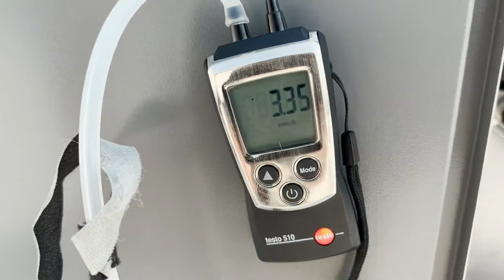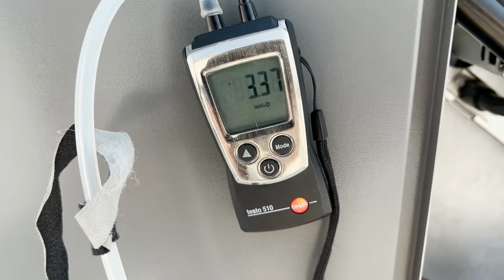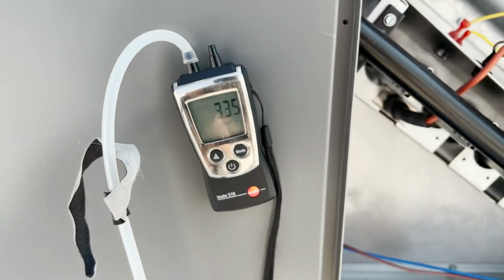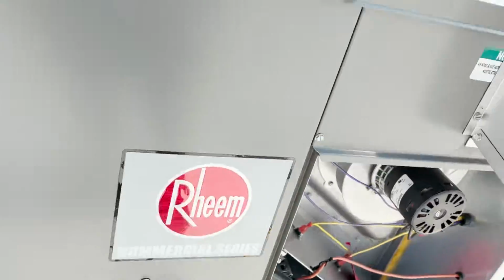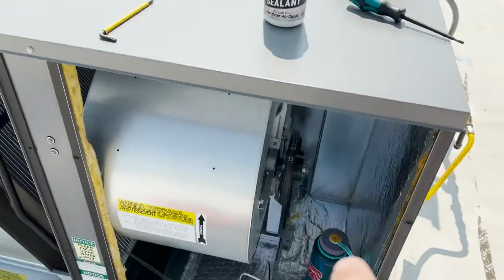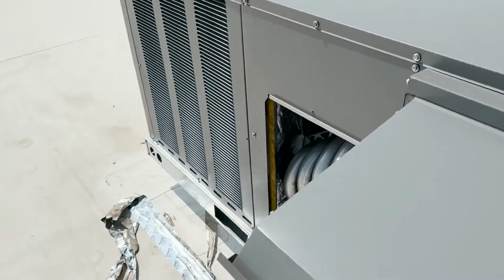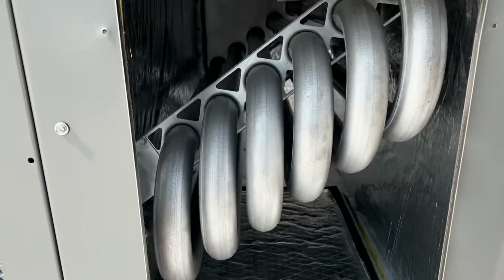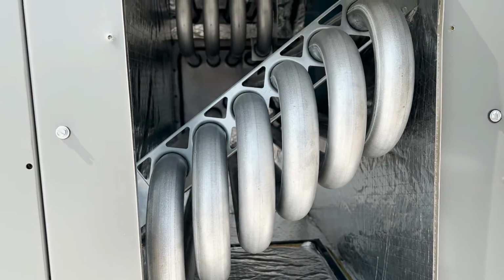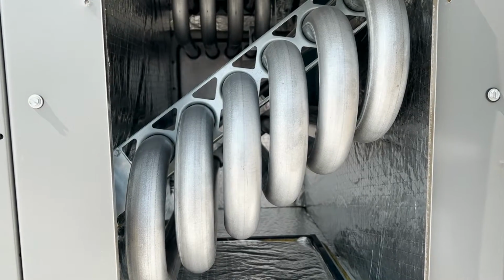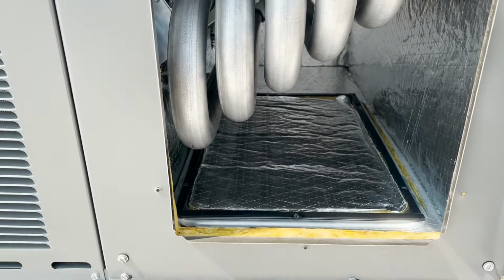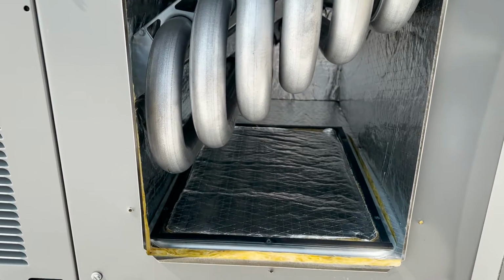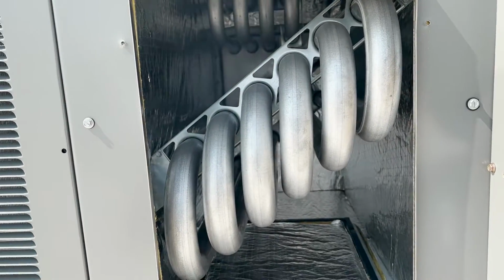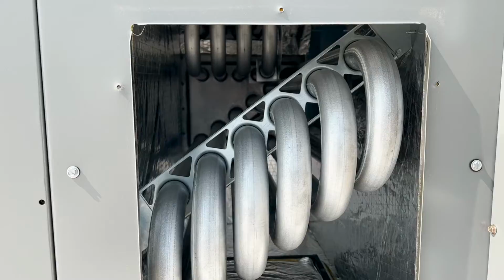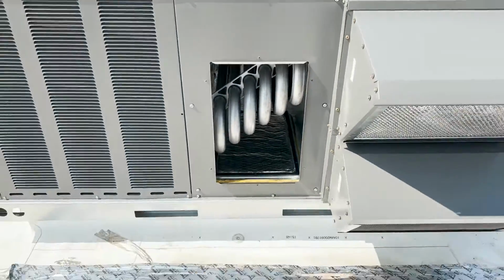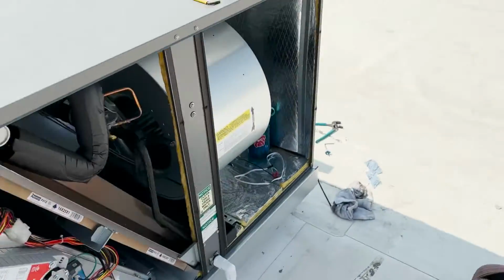Now you see these Rheems, some of them are pretty close, but they almost always need a little bit of help. I like to let this run for just a second to get that blower going. But right now, this is the reason we have this door on, because we're burning off the oil on this heat exchanger, and it's gonna blast out at us here instead of down into the building. Which, if the smoke detectors are live, this will set off the smoke detector, and you're just in for a great day. Woo! Doing everybody a favor.